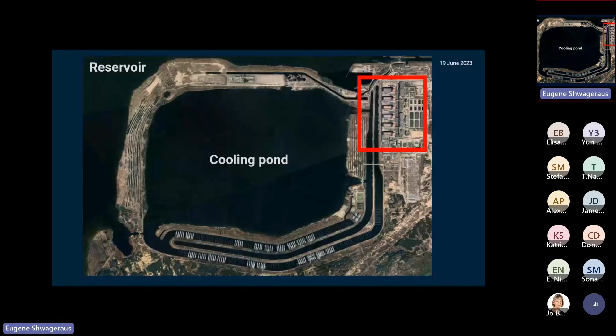Part of it spills directly into the pond through some sparging pipes, and the other part goes through this channel, under this dam, and through a series of other sprinklers, which pick up this hot water, and after cooling it through air, it becomes cold again. Some of the cooling pond's cold water is picked up here as well, and then it returns to the pumping houses. So a quite complicated scheme, but everything is there for a reason.